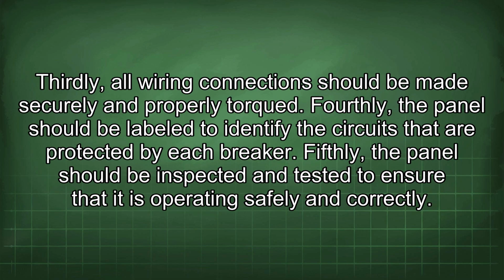Thirdly, all wiring connections should be made securely and properly torqued. Fourthly, the panel should be labeled to identify the circuits that are protected by each breaker. Fifthly, the panel should be inspected and tested to ensure that it is operating safely and correctly.